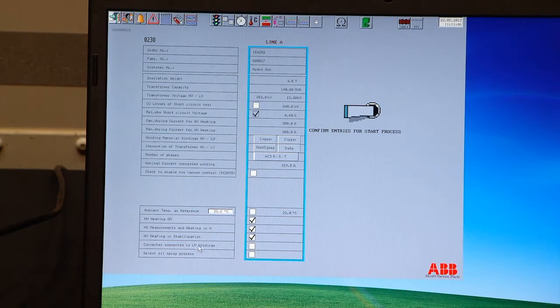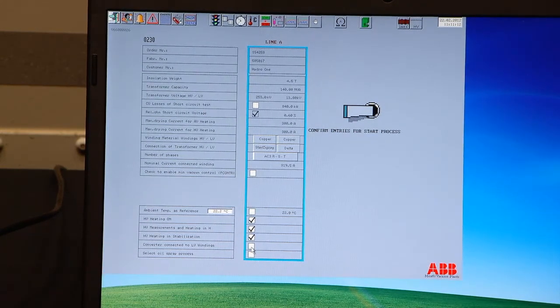The last two is if you're connected to the low voltage winding. Extremely rarely the case for power transformers, but you have the option to, instead of connecting to the high voltage side, connect to the low voltage side and short circuit the high voltage side. The problem you will face is that you don't have current enough to feed it. Output current from the machine. We are limited to 500, so the heating would be very, very slow, close to non-existing, because of the capacity of the low voltage side.